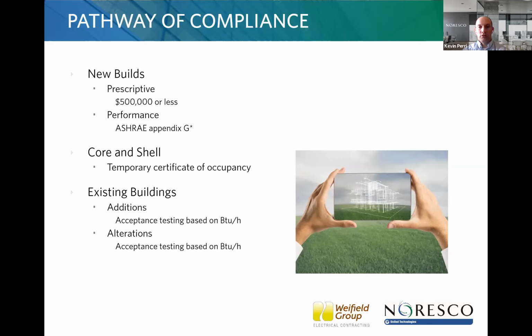And then existing buildings, the 2 amendments that we would like to point out here are for additions and alterations. Existing building additions and alterations do have to do acceptance testing based on the BTU per hour of the mechanical systems and service hot water heating. So just know that that's a little bit different than the standard code. And again, the additions are based on the $500,000 valuation for prescriptive or performance on existing buildings. So if you're doing an alteration or addition that is more than $500,000, then you would have to do a performance pathway, which is Appendix G.